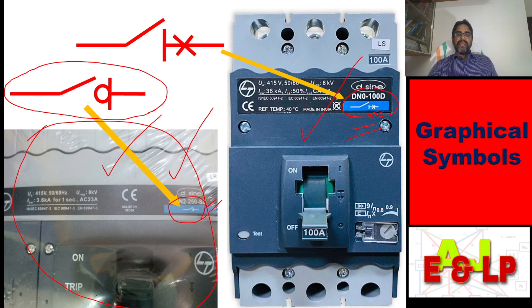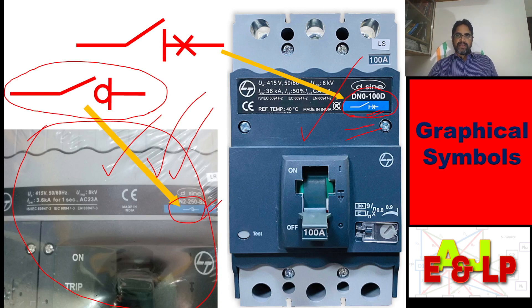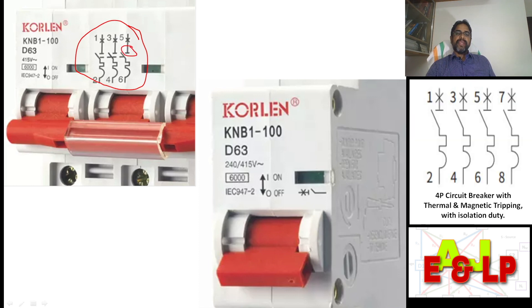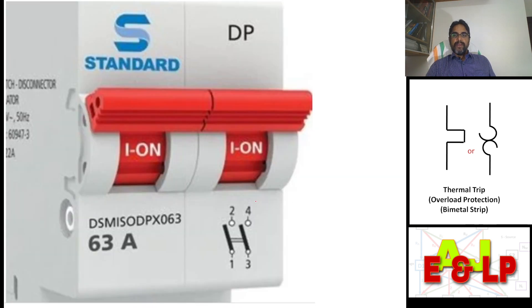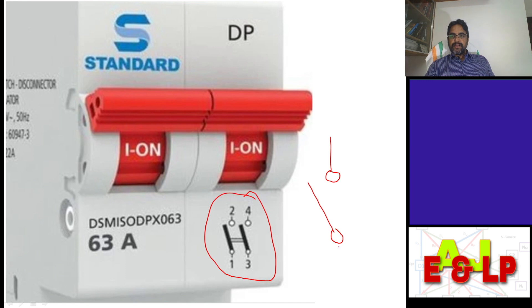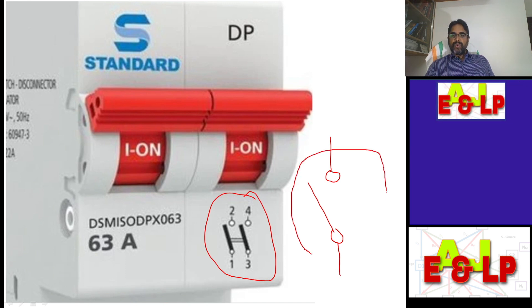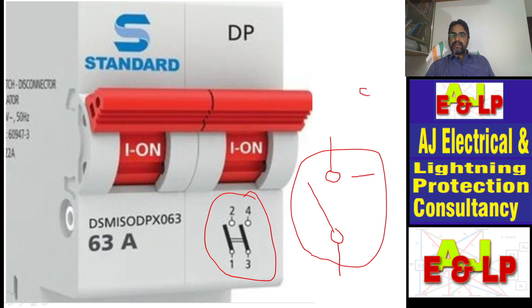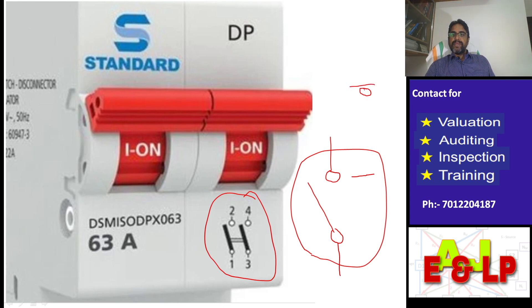In a previous video I mentioned the requirement of an isolator in a fire pump circuit. In such cases, instead of the conventional isolator, we can use this type of MCCB — a switch disconnector without any protections, which can function as a switch as well as an isolator. Now here in this picture it is a circuit breaker with isolation duty and having both trippings. Here there is a conflict — the symbol shown is that of a switch, not even an isolator. If it is an isolator, the horizontal line should be shown there.